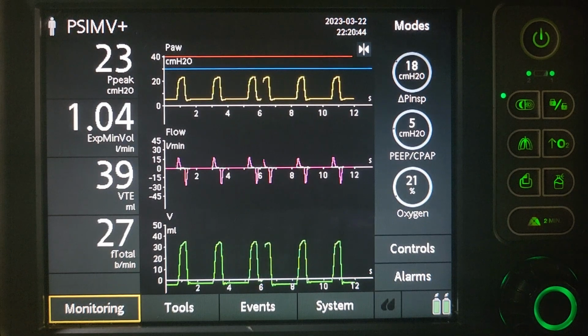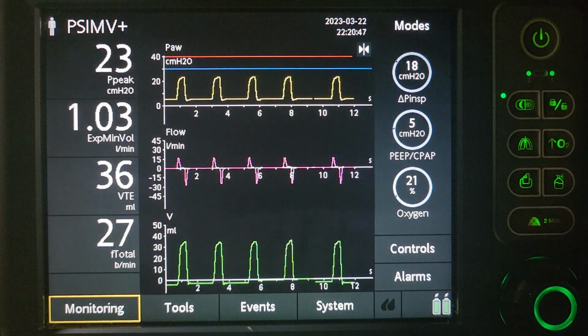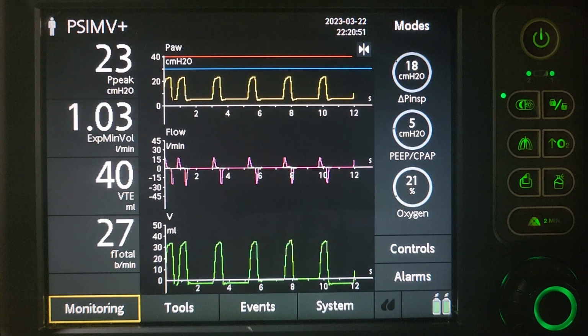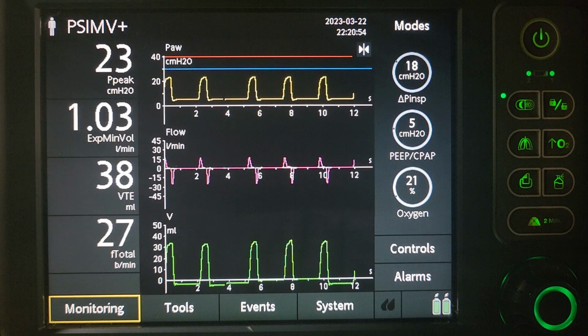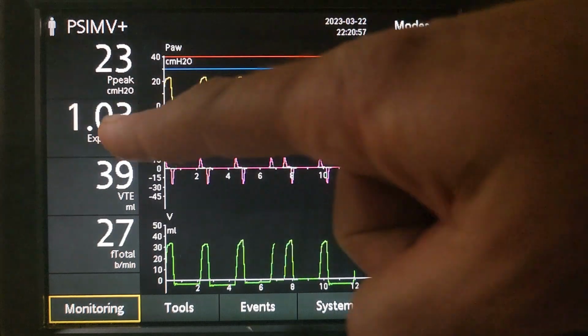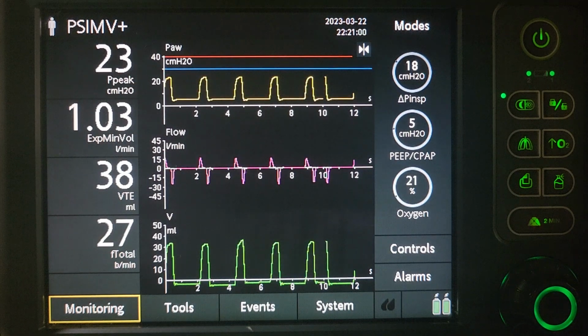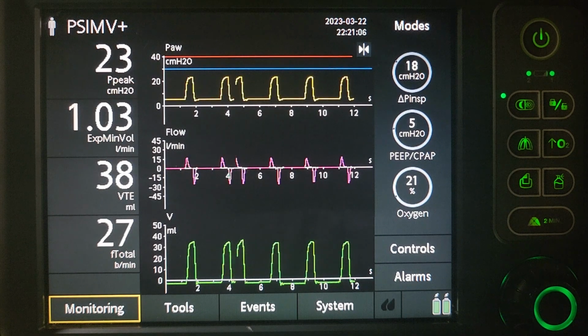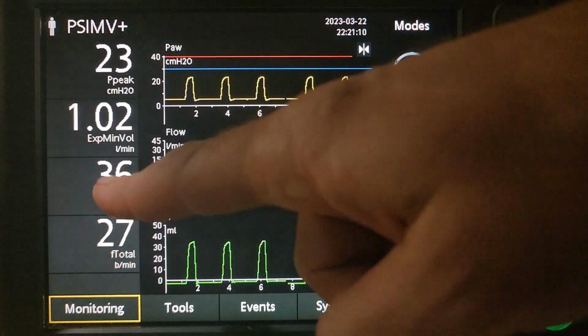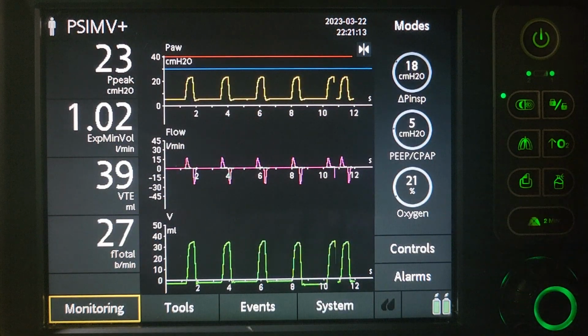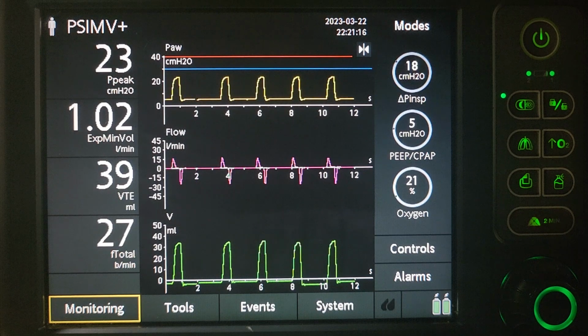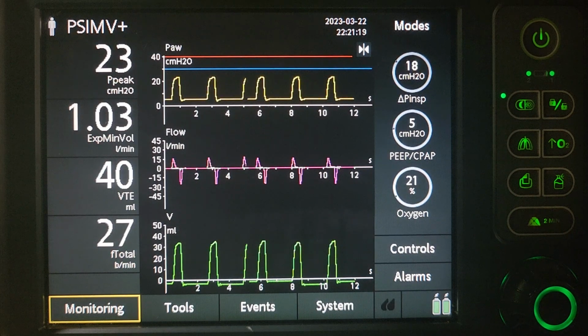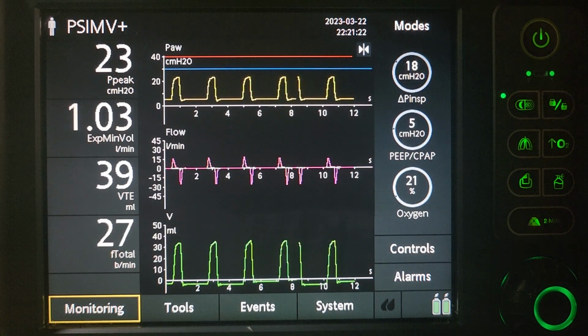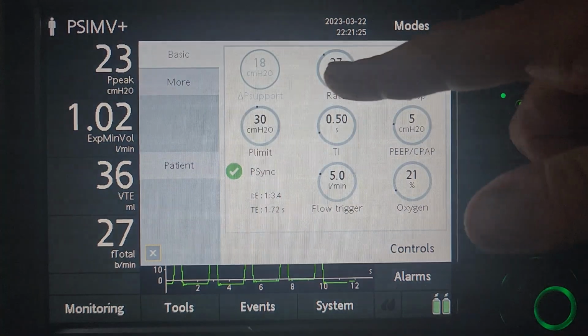So for example, our expiratory minute volume is around 200 per kilo for a normal patient. If we need to increase the expiratory minute volume to blow more CO2 off to maintain them at that lower end tidal CO2 for those severe metabolically acidotic patients, what can we do to increase that expiratory minute volume? Well, we could get a little more tidal volume out of it. Right now we're at 8. We could go as high as 9 or sometimes even 10 if it's easily tolerating, but we can go into our rate here and you'll be able to see as I increase this rate.